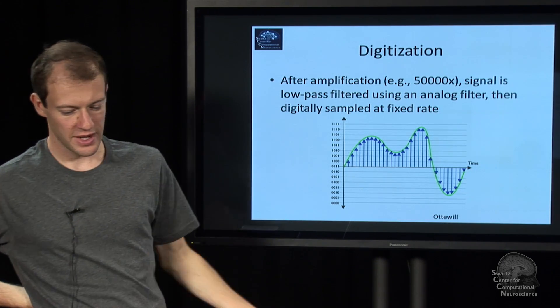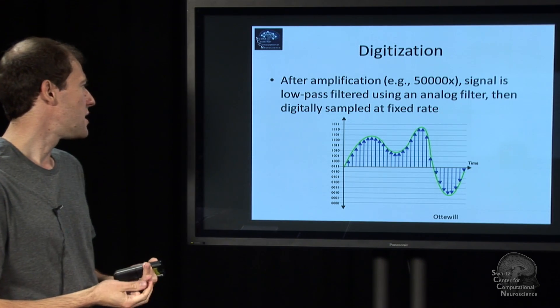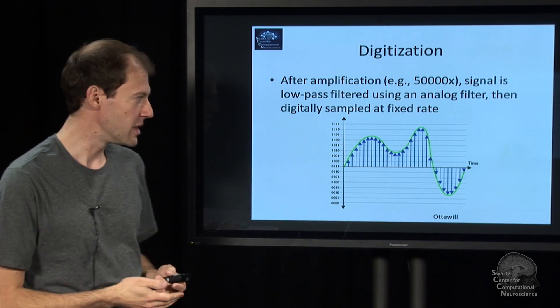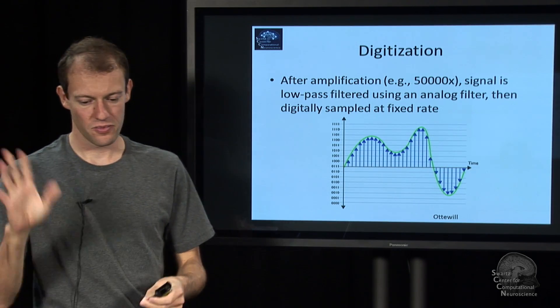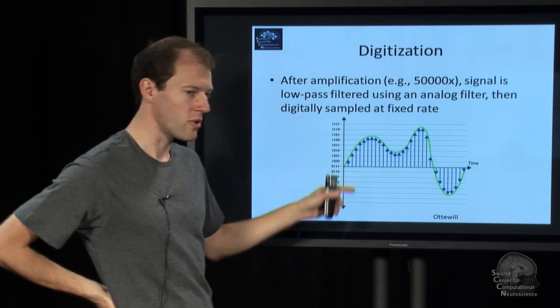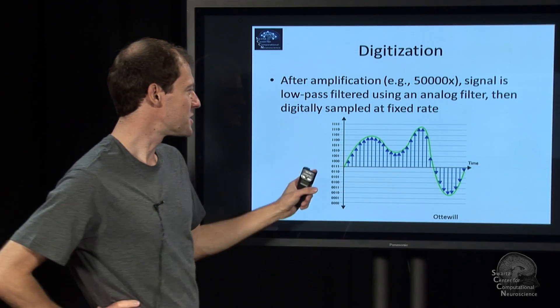Once you've measured the signal in an analog fashion, you need to digitize it for digital processing. What is typically done — based on basic sampling theory — is the signal is low-pass filtered at some frequency, say 200 Hz, and then sampled at particular time points by a digital circuit. That gives you a bit code that tells you how strong the signal is, turning it into a series of numbers. Sometimes this is drawn as a step function, giving the illusion the signal is interpreted that way.